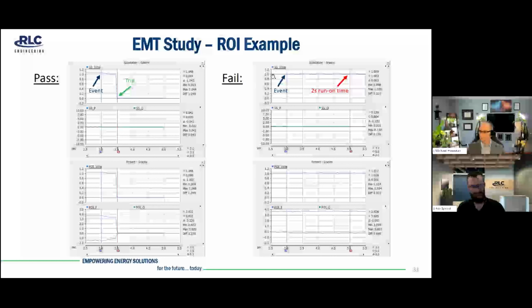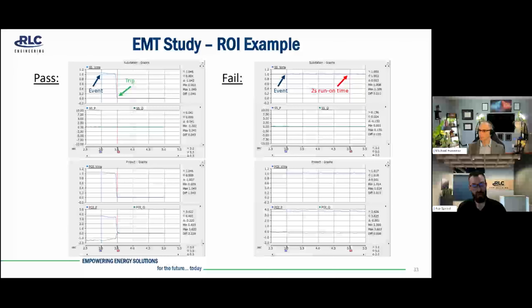However, in contrast, on the right here, we have the same event at 3 seconds, but you can see at 5 seconds, you still have voltage, and that would indicate that your project hasn't tripped, which would also mean you failed your 2-second run-on time criteria per 1547 and would require mitigation either through changing LOMD protection or direct transfer tripping.